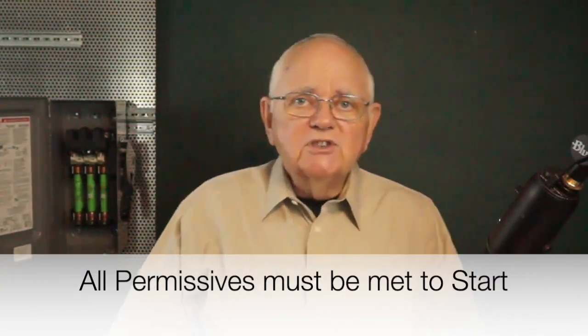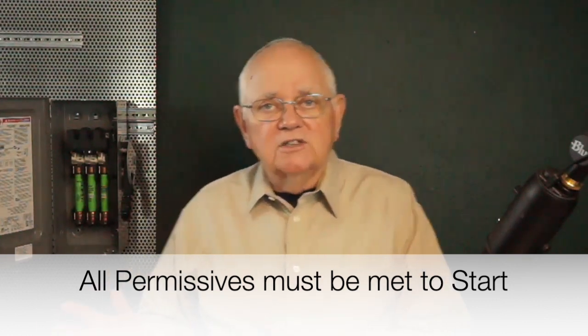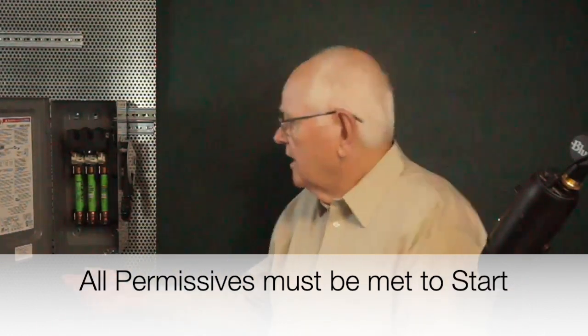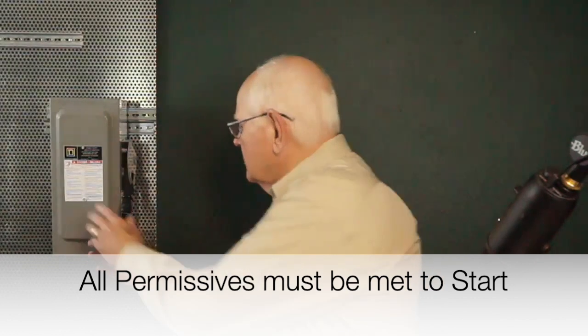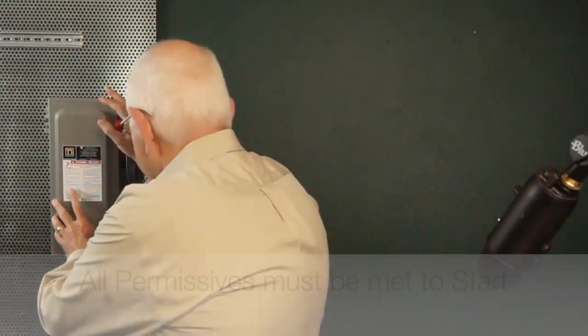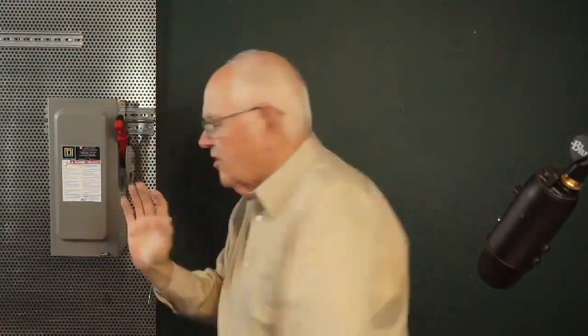All of my permissives have to be met before I can start the machine. So even though I close the door and turn on the power, I go over to hit the start push button, I can't do it unless I meet all of the permissives, meaning all of the requirements in my schematic diagram or my PLC software that would allow me to start that machine, such as, let's say I have an injection molding machine.